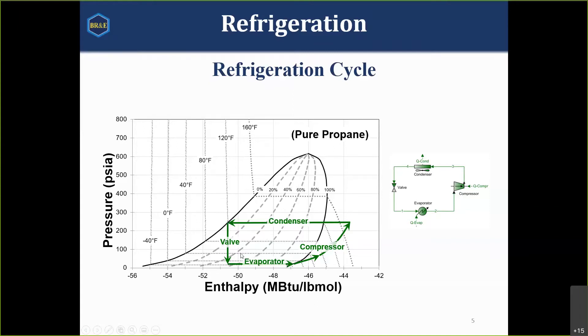Back at our starting point, as we drop the pressure we start to move into the two-phase region — at this point roughly 50 percent vapor, so half liquid, half vapor refrigerant. Since this is a pure refrigerant and we're boiling the liquid at constant temperature, only the liquid portion absorbs heat — the vapor is at constant temperature, so it's just a latent heat effect in the evaporator. For a mixed refrigerant you could have simultaneous sensible and latent heating, but latent heat is still going to be the predominant form of heat pickup.